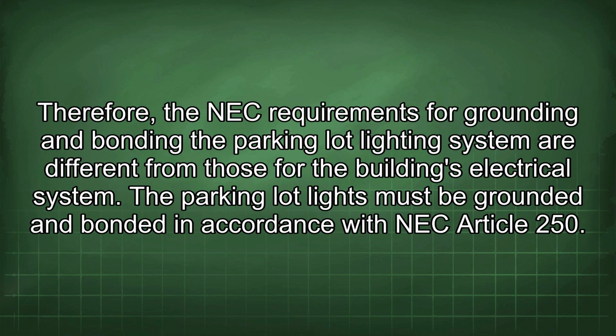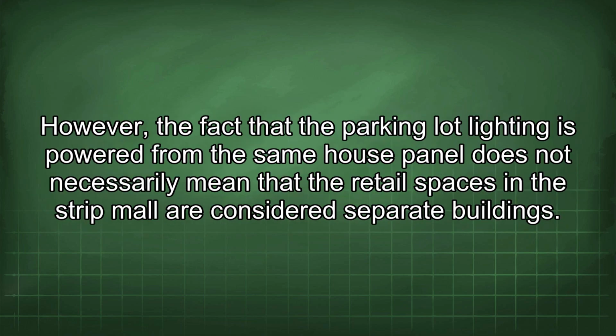The parking lot lights must be grounded and bonded in accordance with NEC Article 250. However, the fact that the parking lot lighting is powered from the same house panel does not necessarily mean that the retail spaces in the strip mall are considered separate buildings.